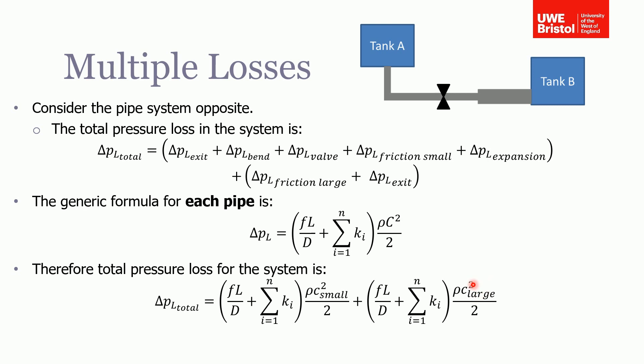So you just need to be aware that you use the correct velocity for each pipe, and if there's a change in material or a change in diameter, then you need to split your network up into different sections and add all those sections together.